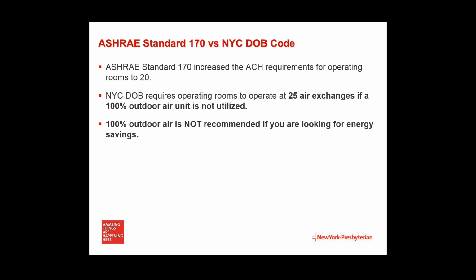The one thing that we have at a disadvantage compared to other places is that the ASHRAE standard will simply increase the air exchange requirements for operating rooms to 20. Unfortunately for us, New York City, the Department of Buildings requires operating rooms to operate at 25 air exchanges if a 100% outdoor air unit is not utilized. And because of the change in seasons, 100% outdoor air is not recommended if you're looking for energy savings.